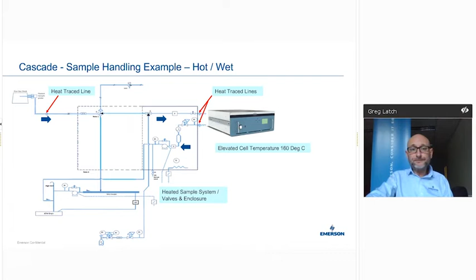This gives you a brief overview of some of the components of interest on this one application in particular. It's not unusual in any way, shape or form. We're now looking at NO, NO2 and N2O without any NOx conversion, which is a direct measurement, as opposed to calculating out NOx. CO, CO2, sulphur dioxide, O2, where we expect potential residual and carryover. Probably the strange one, everybody will be looking at it and going, geez, it's a hell of a lot of water.